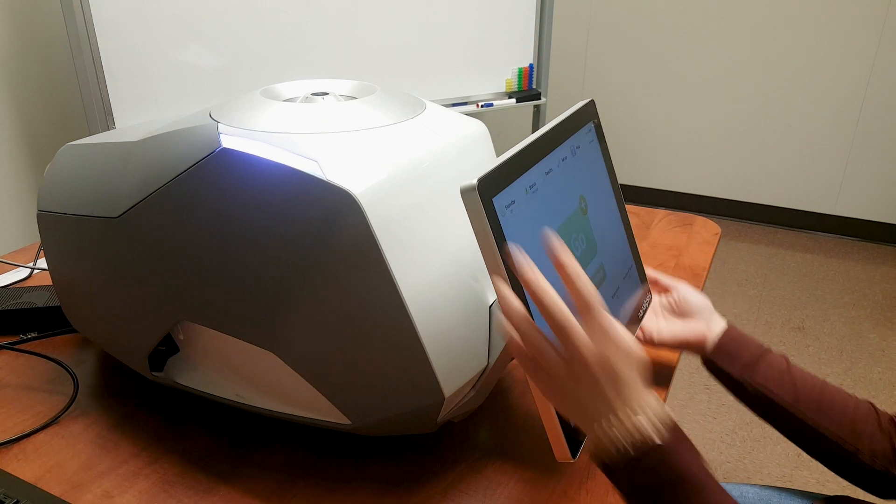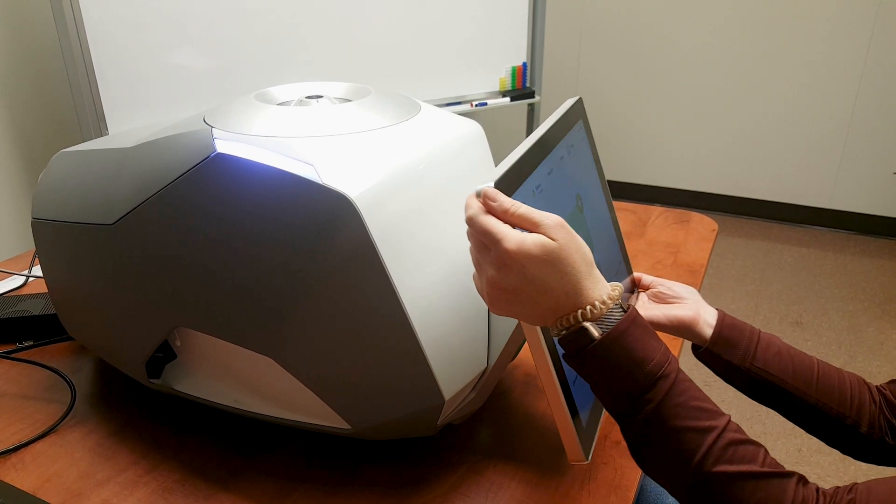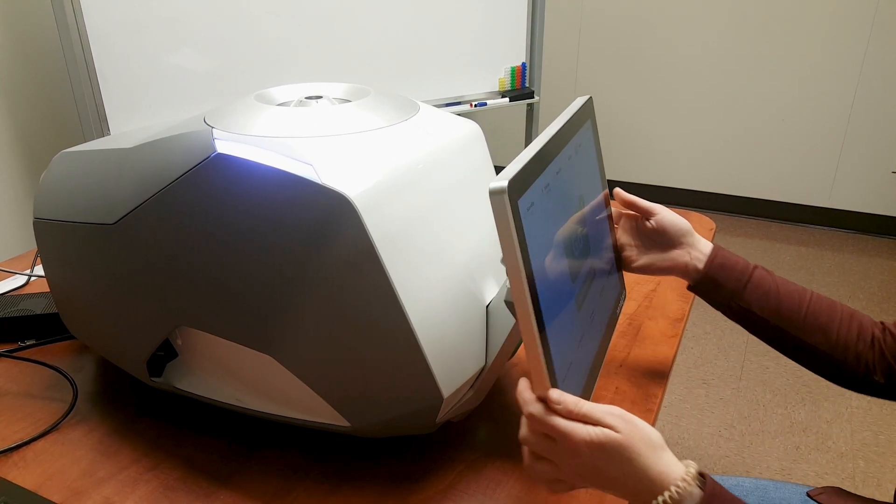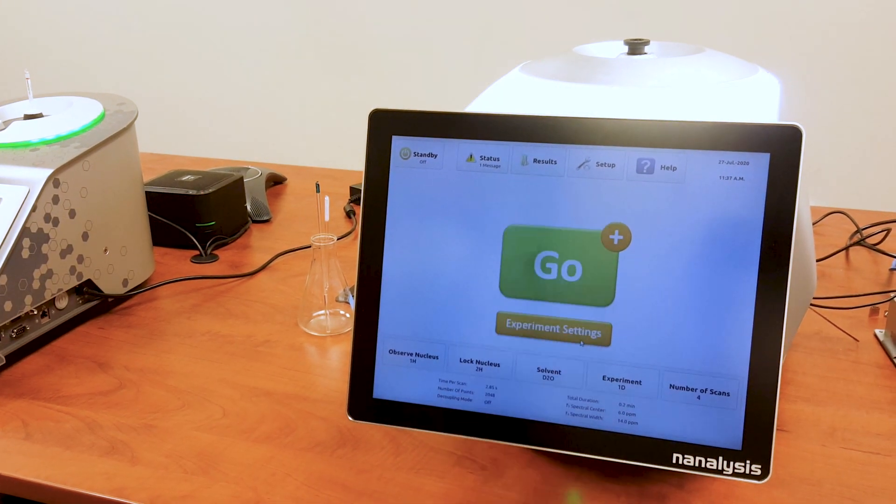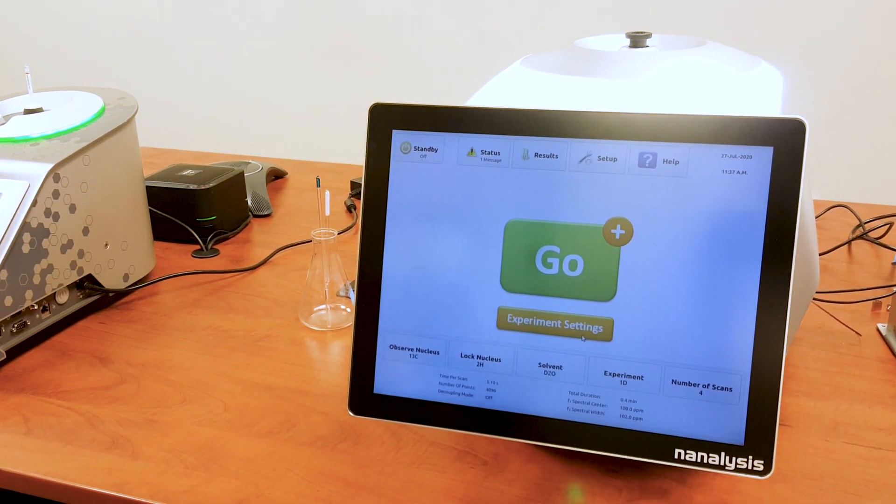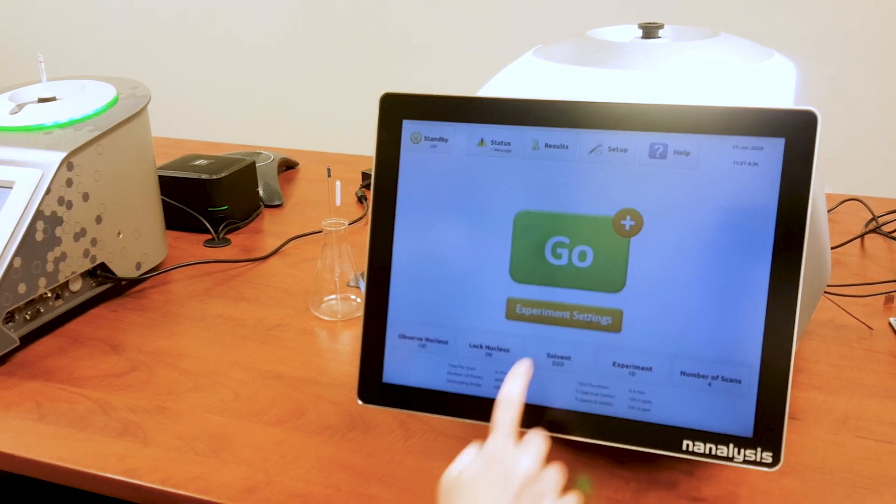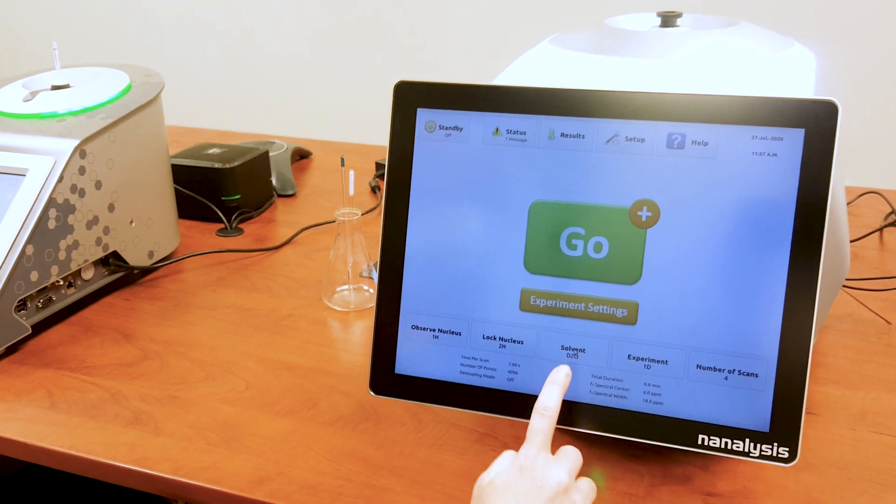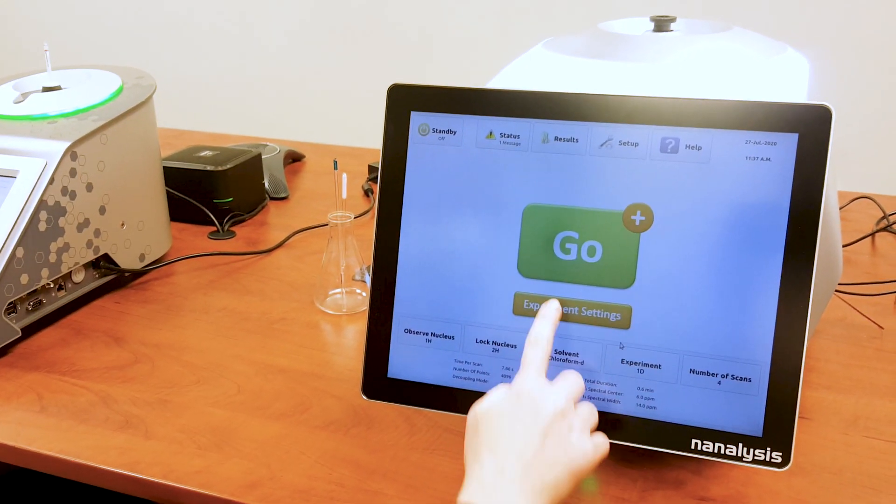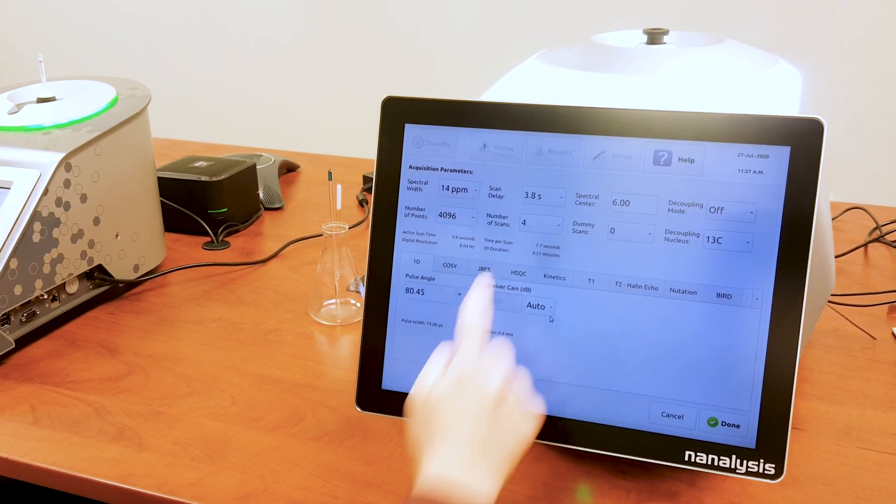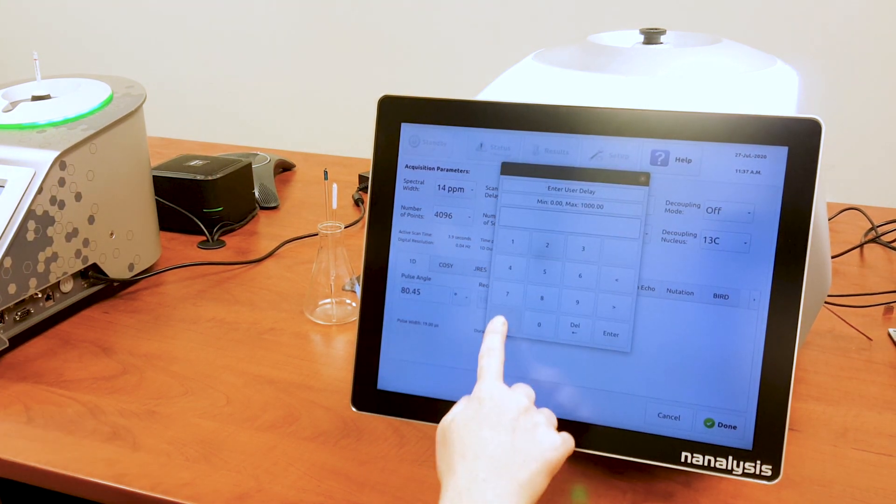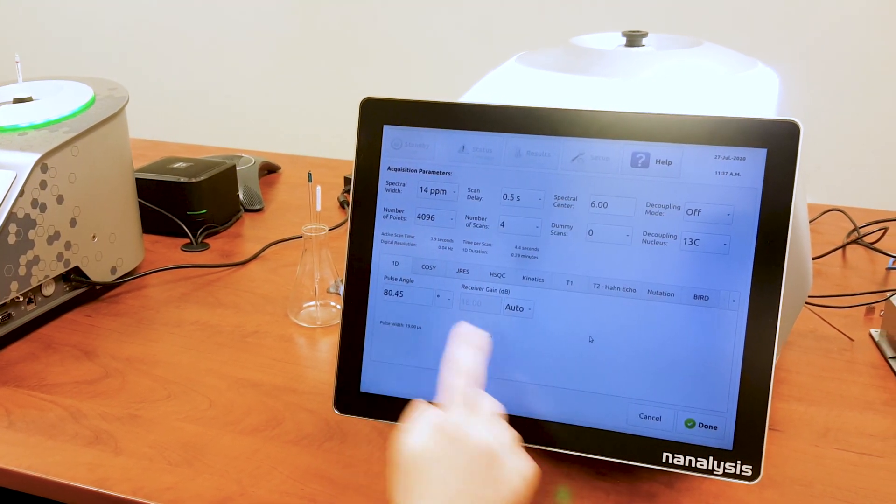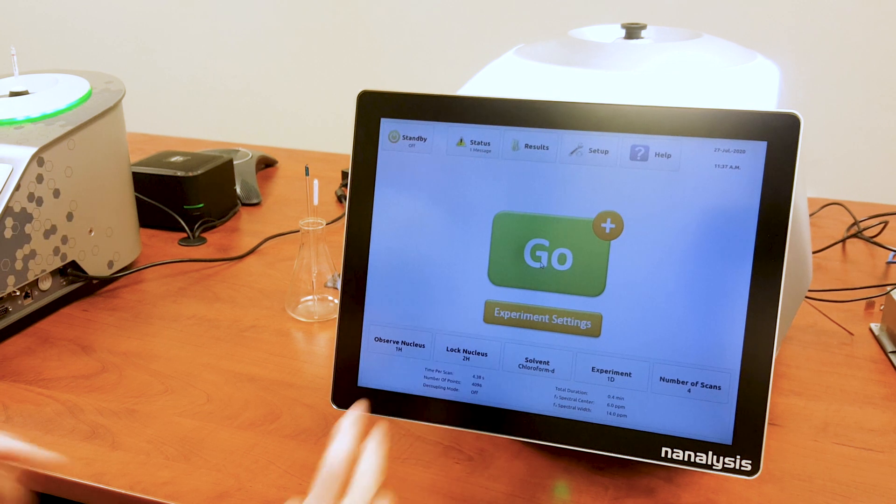The OneTouch software provides the same automation and easy modification as the 60 MHz model. It allows the user to load common experiments and change basic acquisition parameters like spectral width, inter-scan delay, etc. The user can also use either the drop-down menu or input the desired value using the customization keyboard.